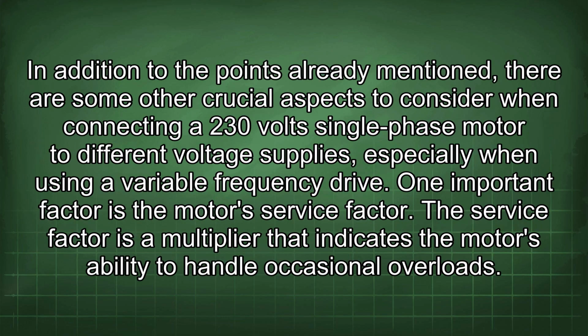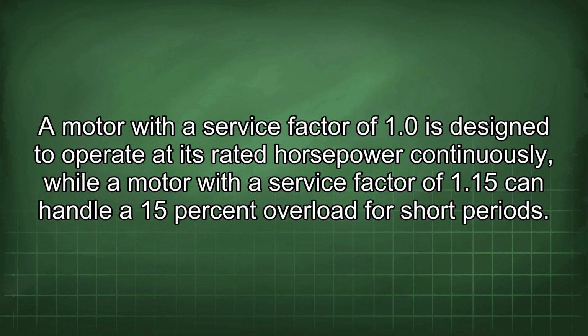In addition to the points already mentioned, there are some other crucial aspects to consider when connecting a 230-volt single-phase motor to different voltage supplies, especially when using a variable frequency drive. One important factor is the motor service factor. The service factor is a multiplier that indicates the motor's ability to handle occasional overloads. A motor with a service factor of 1.0 is designed to operate at its rated horsepower continuously, while a motor with a service factor of 1.15 can handle a 15% overload for short periods.